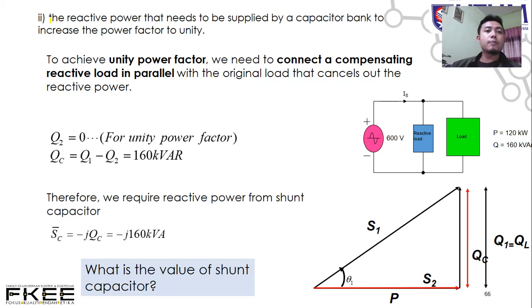Determine the reactive power needs to be supplied by a capacitor bank to increase power factor to unity. Power factor unity means power factor equal to 1. To achieve unity power factor, we need to connect a compensating reactive load in parallel with the original load that cancels out the reactive power.